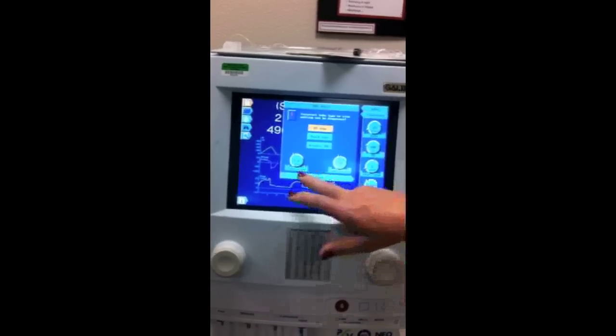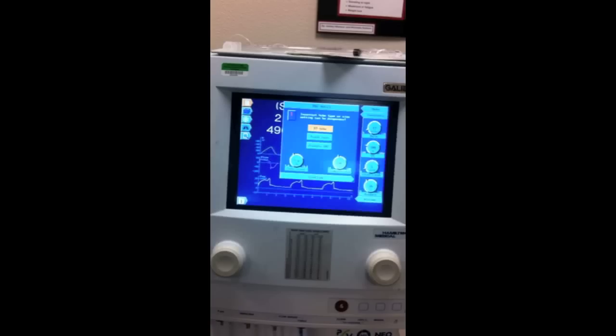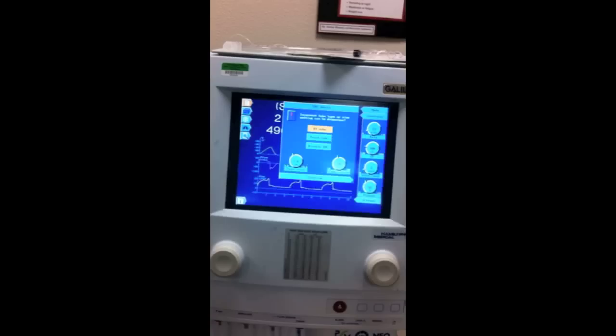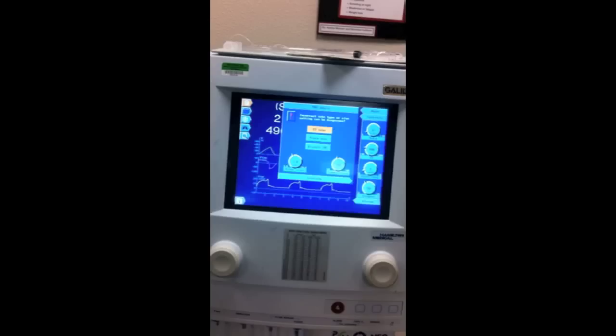We can tell the ventilator that my patient has a size 8 ET tube, and I want you to compensate for 50% of the resistance. You could have it compensate for 100%, 75%, 50%, 25%, whatever you want. But that will give a precise amount, similar to pressure support, to give the exact amount of help that's needed to overcome the resistance from the ET tube. They've calculated that if a patient has a size 8 ET tube, this is exactly how much assistance that patient needs to overcome the resistance of it were they not intubated.